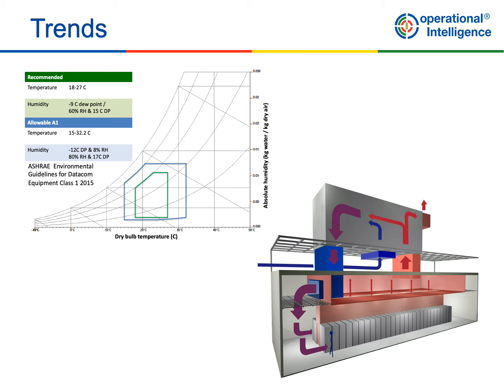Another trend is higher temperature operation. The diagram on the top left shows the ASHRAE recommended and A1 allowable ranges for air temperatures at the inlet of IT equipment. So this is a psychrometric chart which has been defined with Technical Committee 9.9, incorporating all the major hardware vendors. These ranges have expanded in recent years, and this is able to drive higher temperature operation, which allows reduced use of refrigeration and also more free cooling hours.